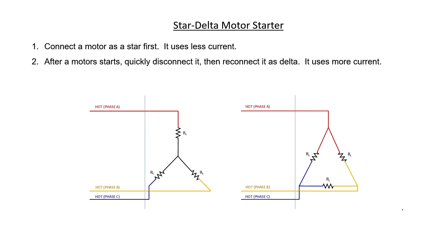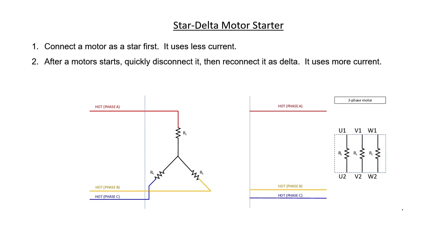All you need is a sequence of switches. There are six different connections on a three-phase motor. Let's count up all the connections. Imagine that I have a motor connected in the star configuration. There's one of its three coils, there's another coil, and then there is its third coil. There are six different places where I need to make a connection. Let's go ahead and connect this motor in the star configuration so that the motor that I have here modeled as a box will match the circuit diagram to the left. This is the U1 connection to the motor. Phase A is connected to U1. Phase B is connected over here to V1. Phase C is connected to W1. The other sides of these three coils, U2, V2, and W2, are connected to one another to form the star point.